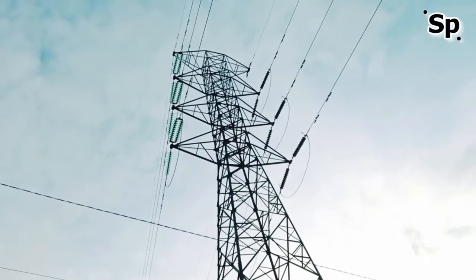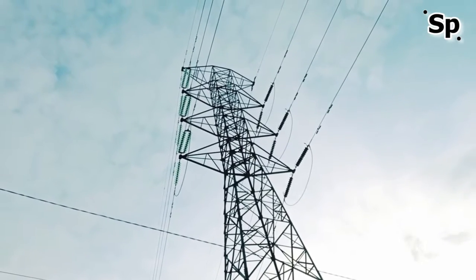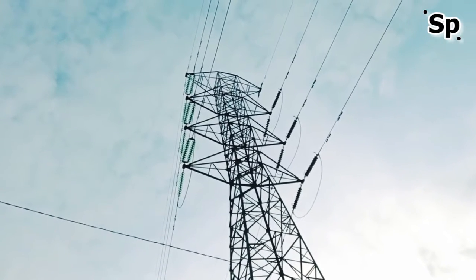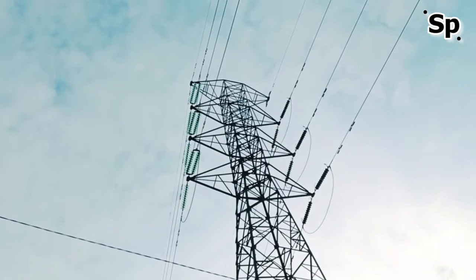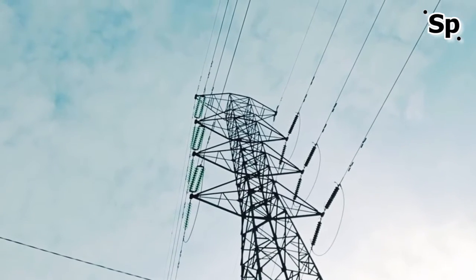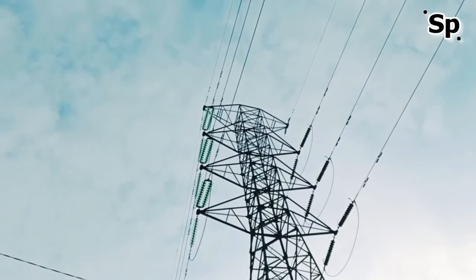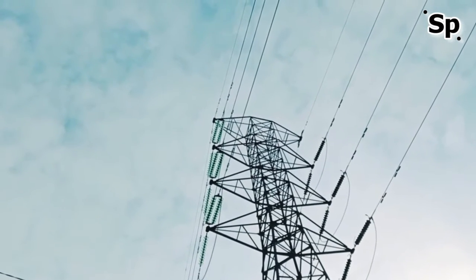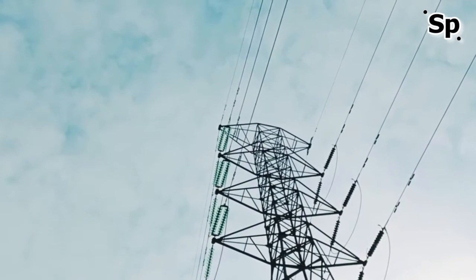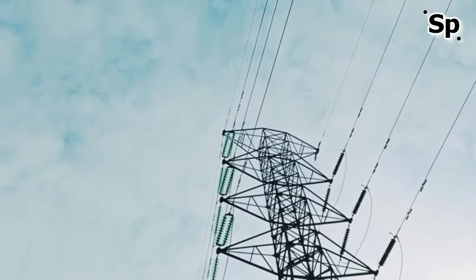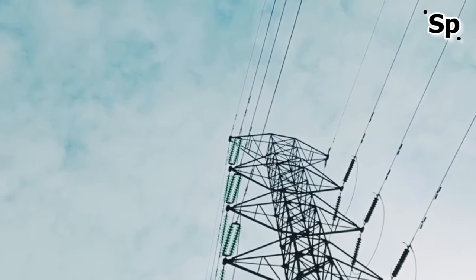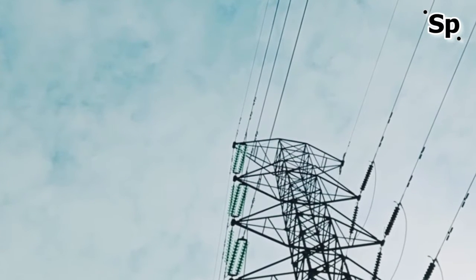Conductor sizes range from 12 square millimeters, number 6 American wire gauge, to 750 square millimeters, 1,590,000 circular mils area, with varying resistance and current carrying capacity. For large conductors, more than a few centimeters in diameter, at power frequency, much of the current flow is concentrated near the surface due to the skin effect.